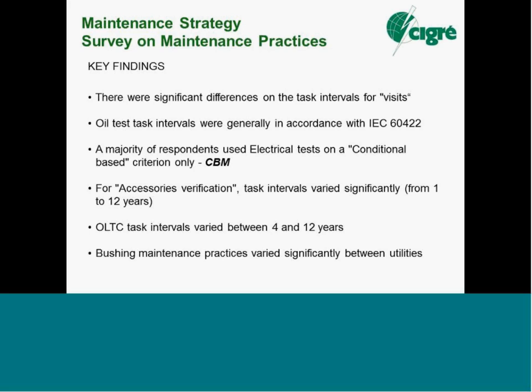Maintenance practices varied significantly between the utilities. One thing that did come from a CIGRE reliability survey, going back to 1994, is that the components of the transformer that cause expensive failure are usually the bushings, the tap changers, or the active part, the windings in the transformer. So there's a clear message from that reliability survey that there should be some effort in realising what causes expensive failure. Those three things, there should be some effort in monitoring of those things.